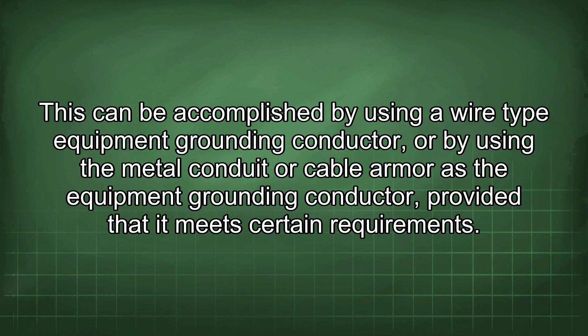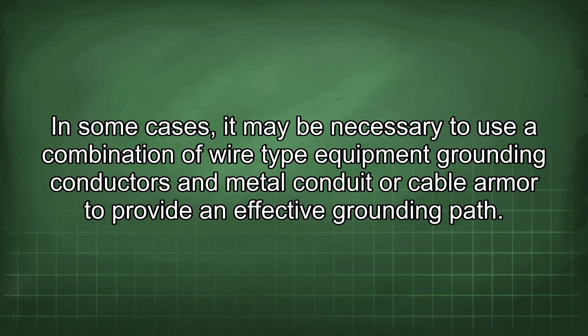In some cases, it may be necessary to use a combination of wire-type equipment grounding conductors and metal conduit or cable armor to provide an effective grounding path. For example, if the metal conduit is not continuous, it may be necessary to supplement it with a wire-type equipment grounding conductor to ensure that there is a continuous grounding path back to the panel board.